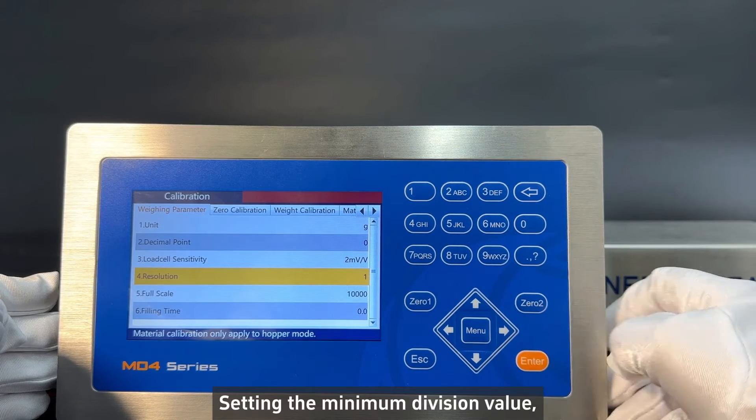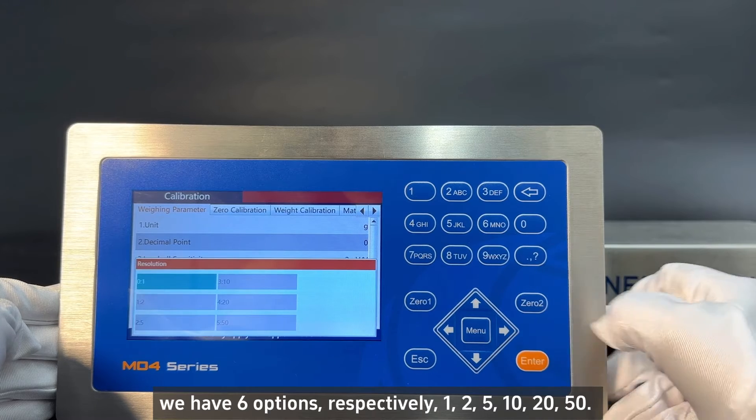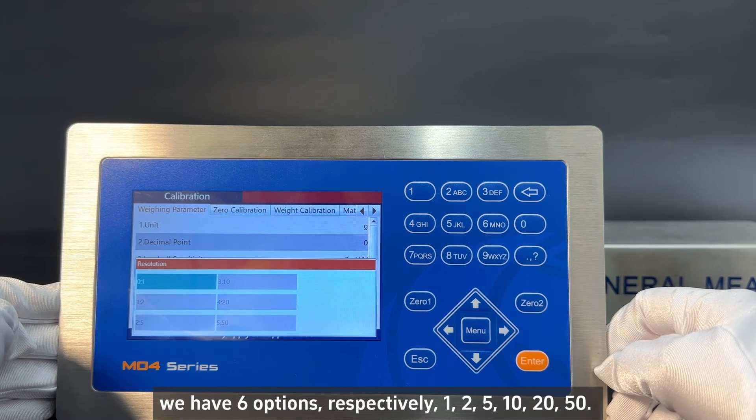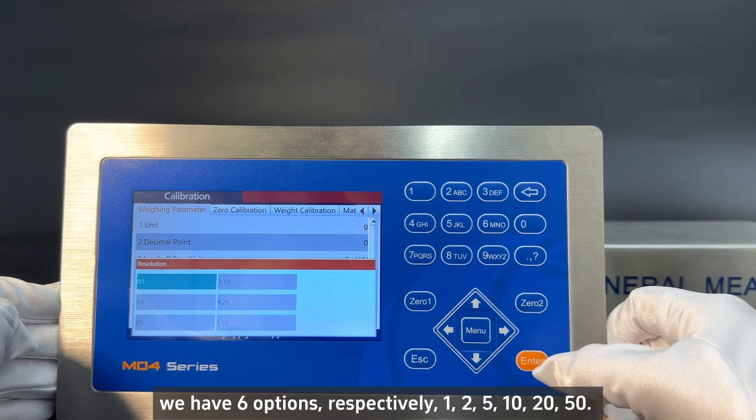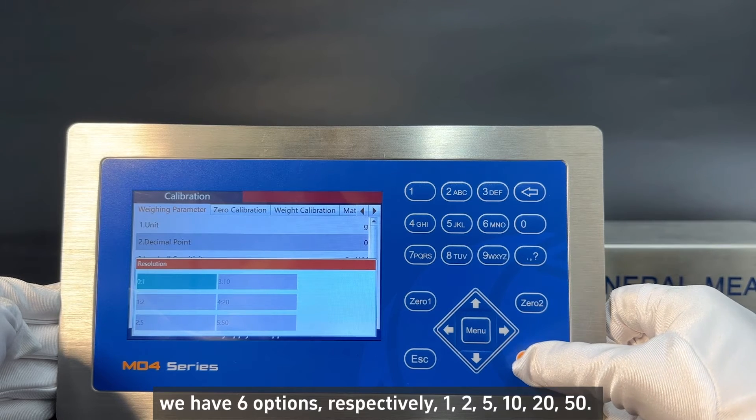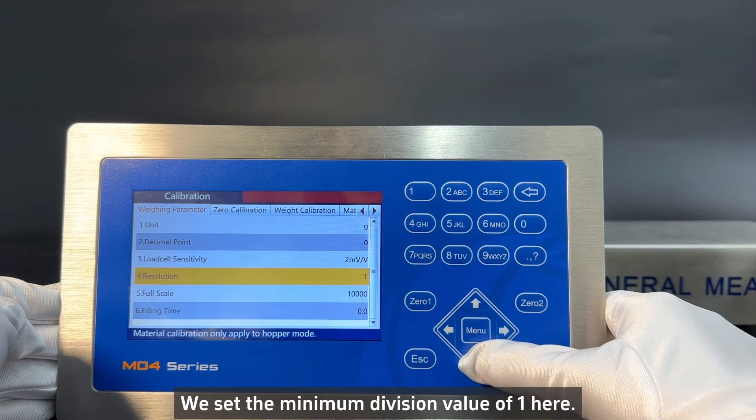Setting the minimum division value. Press the enter. We have six options, respectively: 1, 2, 5, 10, 20, 50. We set the minimum division value of 1 here.